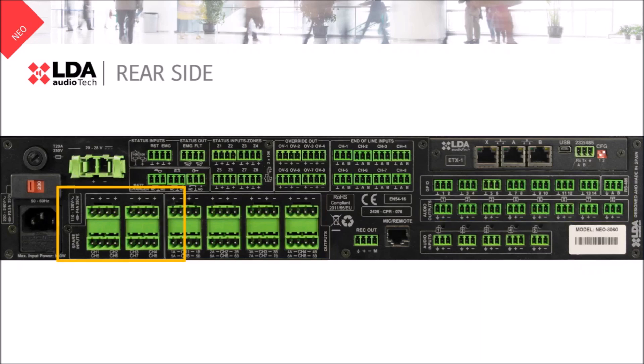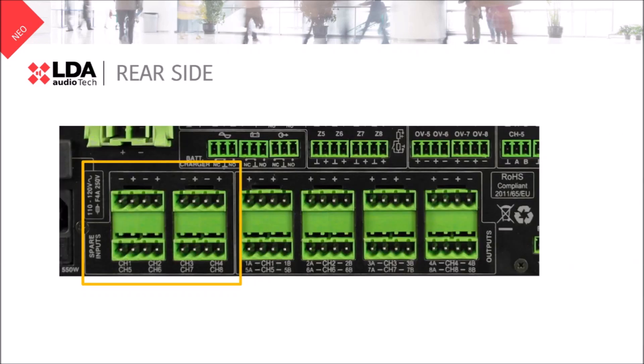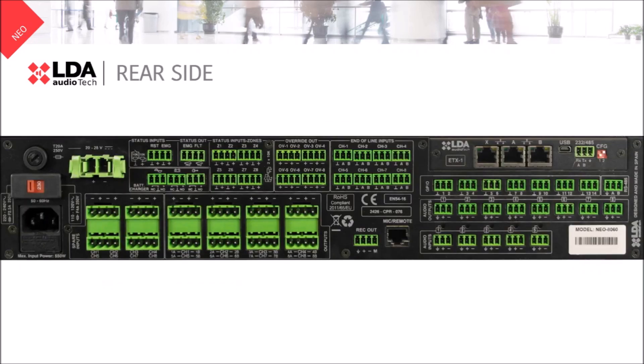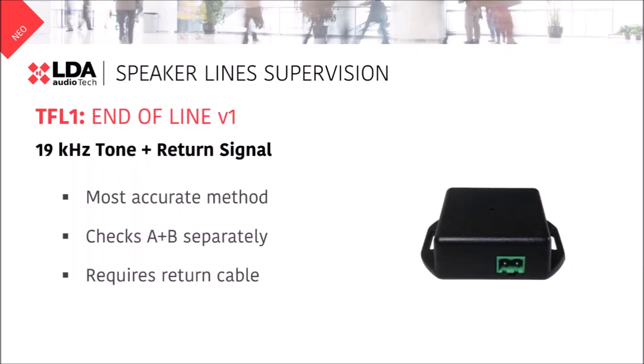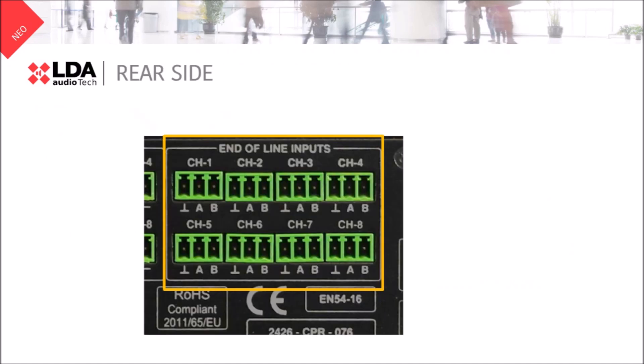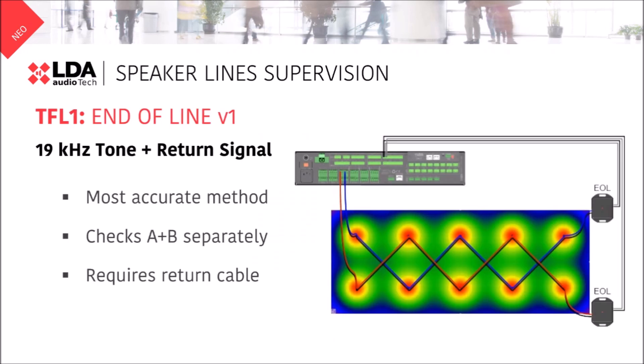On the left side of the amplifier outputs, we have the spare inputs. They are used to make the necessary connections whenever you need a backup amplifier. After the speaker lines, we will need our end-of-line device. We call it TFL. Please note only version 1 of this device needs the return cable. The return cable will be connected in Neo into these inputs, creating a system like the one in the picture.